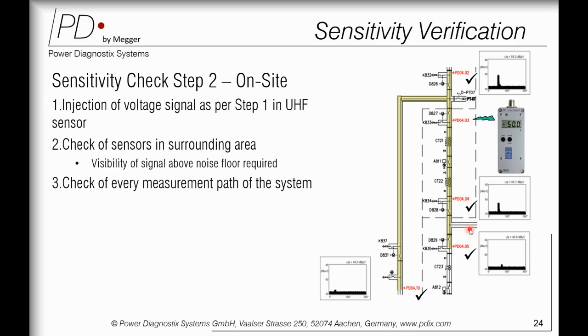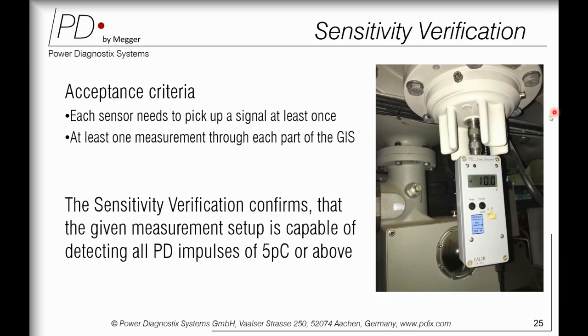But the problem is, the more it travels, the higher the signal attenuation. The signal gets dropped and becomes weaker. So there is no thumb rule for what the exact value should be. The only thing is you should get some peak, or some signal showing that the sensor has captured something. So once you have injected from here, if all your sensors are capturing, that means even if a 5 pC PD happens in your complete environment, the UHF sensors are more than sufficient to capture it. This is one image of the pulse injector. You connect here, inject the voltage, and you will see it in the PD monitoring system.